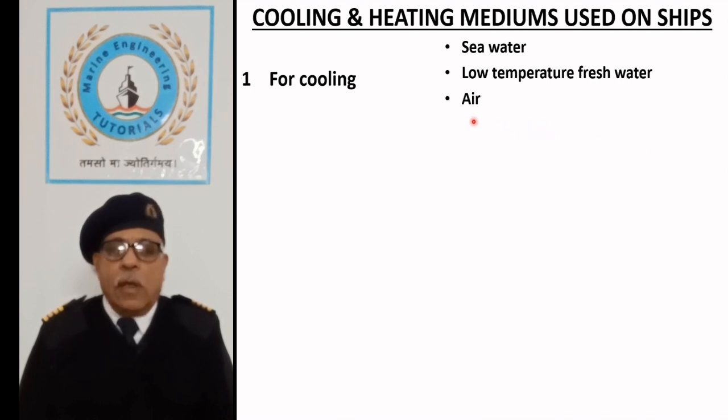Air. Air is used as cooling fluid on small systems. Water-cooled heat exchangers are much smaller in size as compared to air cooling because water can absorb 4.23 times more heat than air for the same mass of both fluids. At the same time, seawater temperature is usually lower than atmospheric air temperature, which further improves the heat transfer.